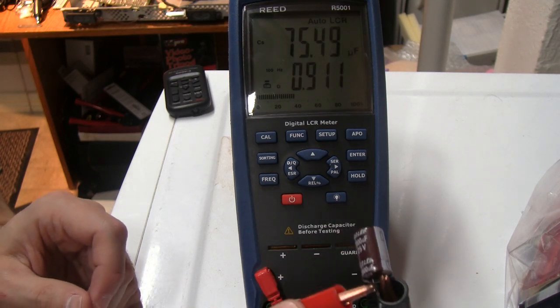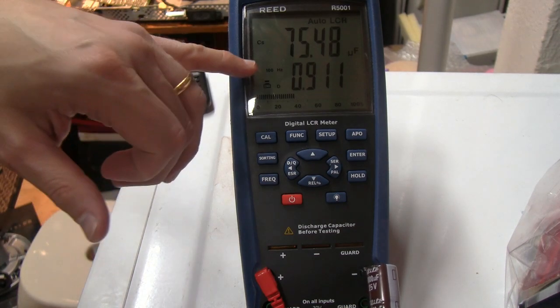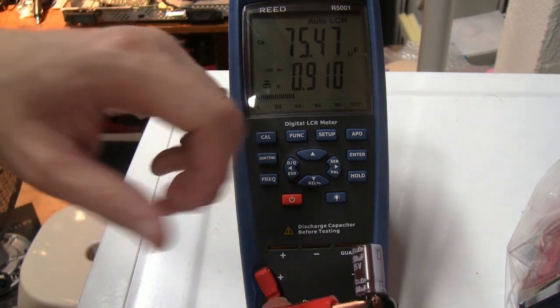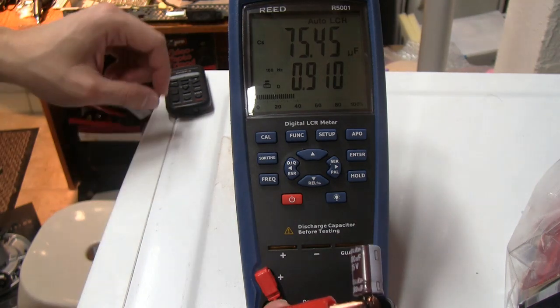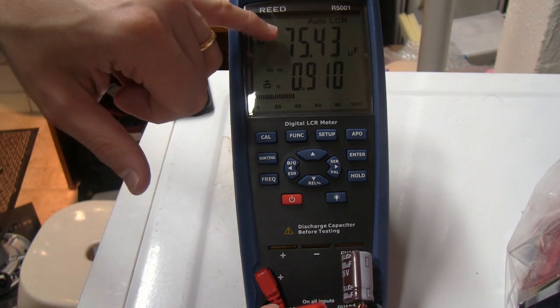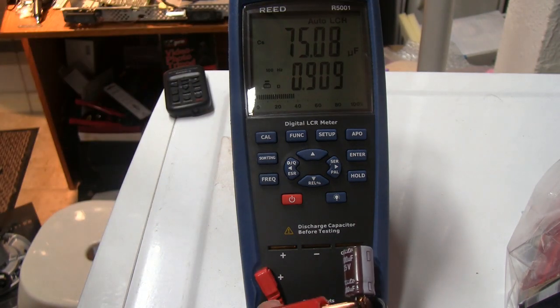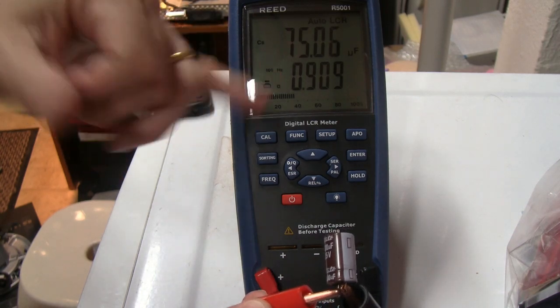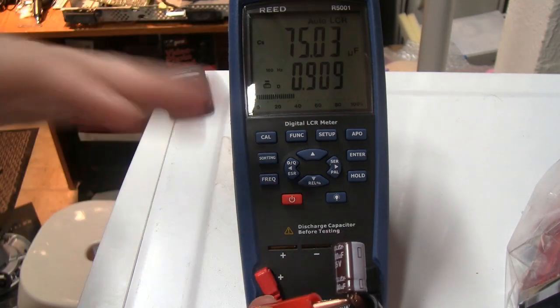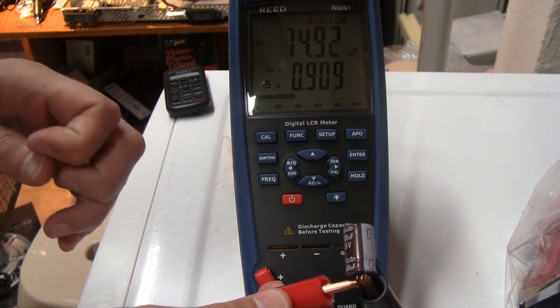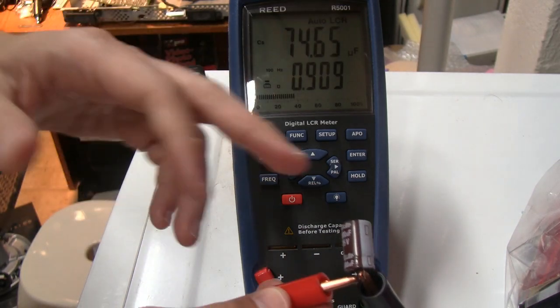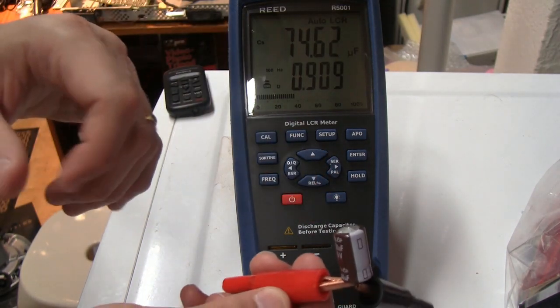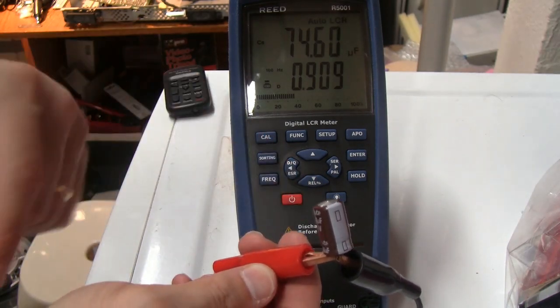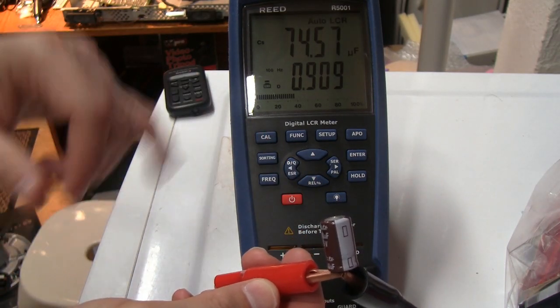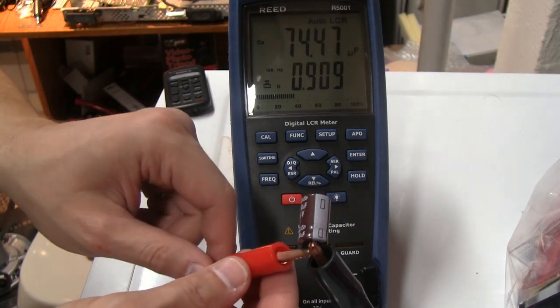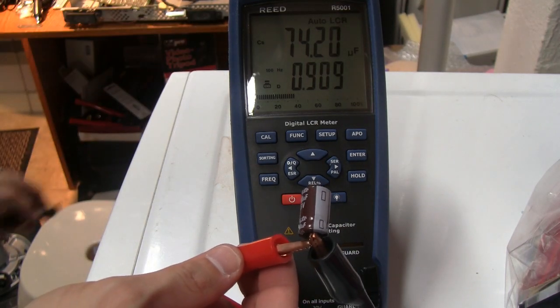Okay, so at 100 hertz this is supposed to have 1000 microfarads. We're seeing 75 microfarads, and there's a lot of leakage in here. Well, this is the dissipation factor. Typically for this capacitor it is 0.1, 0.2 tops. This is 0.9. There's a lot of leakage, and it's no wonder. It's this puffy thing here that just messes up your world. 74 microfarads. That's truly a no good guy.